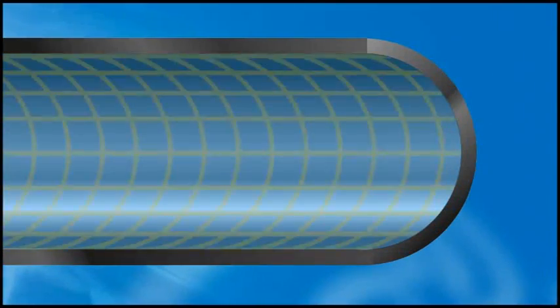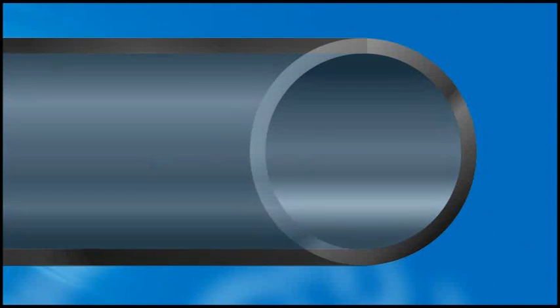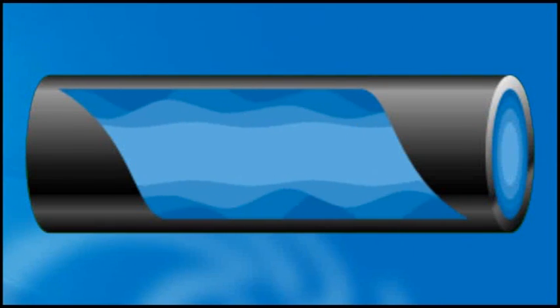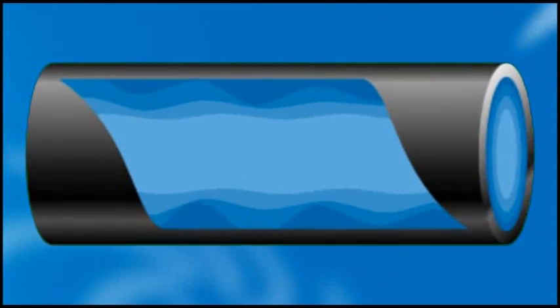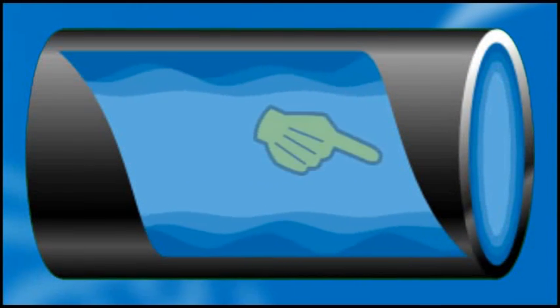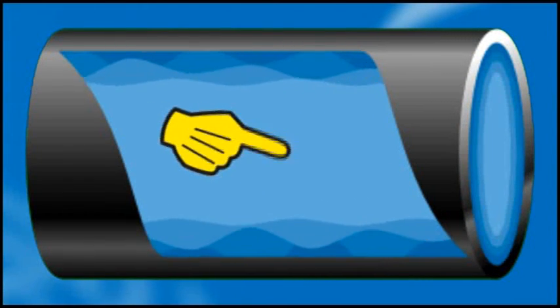The internal surface area of your pipe can make a huge difference too. In our example, we will be using polythene pipe. When the diameter of the pipe is increased, friction loss is reduced. More water can flow through the middle, with less touching the walls of the pipes where friction loss occurs.